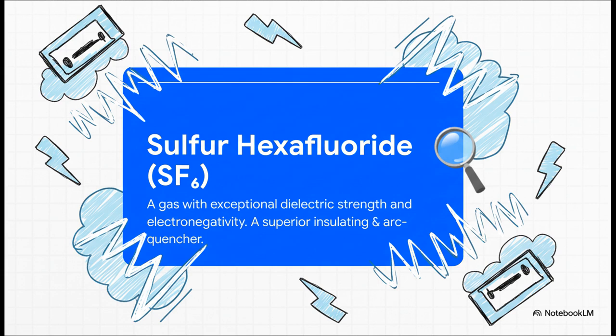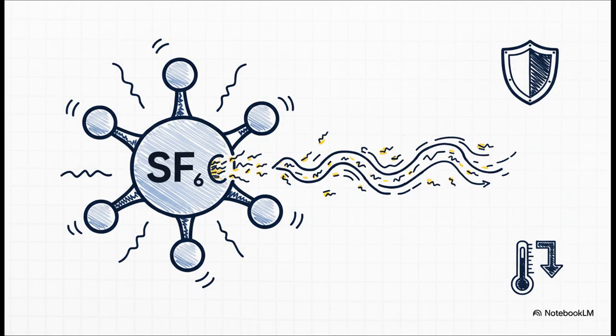That's its electronegativity. So what does that even mean? Well, it means the SF6 molecules are incredibly greedy for any free electrons they can find. That electrical arc, it's basically just a river of free-flowing electrons. So when the SF6 gas hits that arc, it acts like a super absorbent sponge, just soaking up all those electrons and completely smothering the arc at its very source.